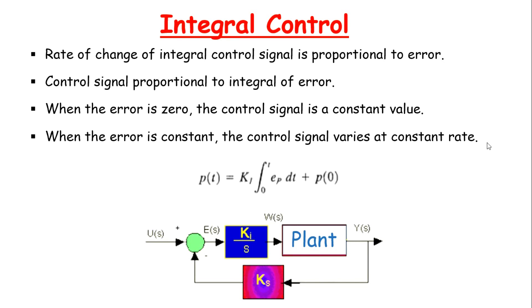The integral equation is: p(t) = Ki × ∫₀ᵗ ep(t) dt + p(0), where p(0) is the controller output when the integral action starts. The gain Ki expresses how much controller output is needed for every percent-time accumulation of error.